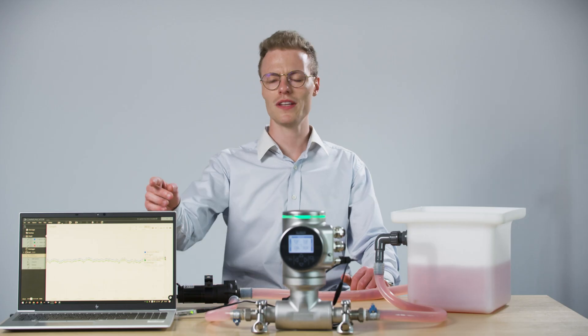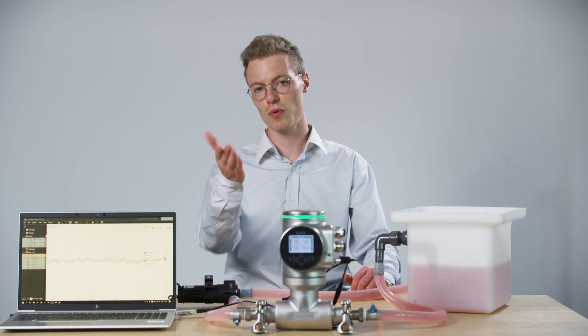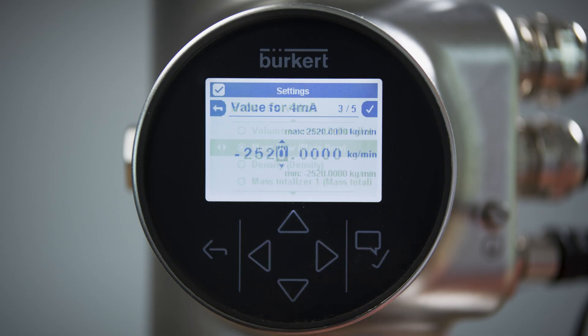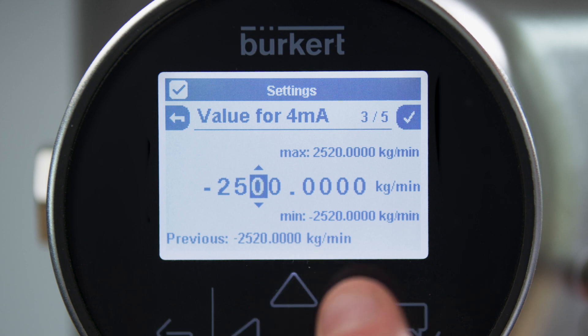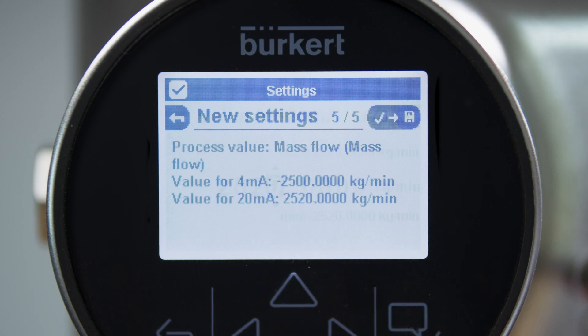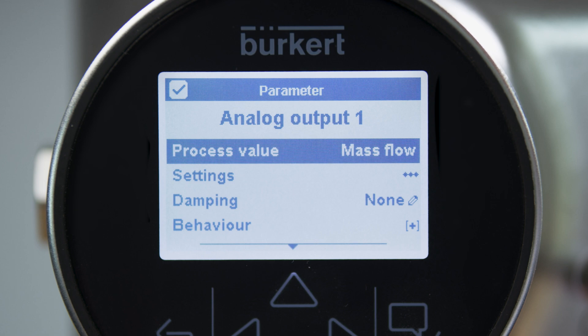Now, how do we transmit this information to your process controller? Mass flow can, for instance, be output in the form of a 4-20 milliamp signal, for which the full range can be selected at will.